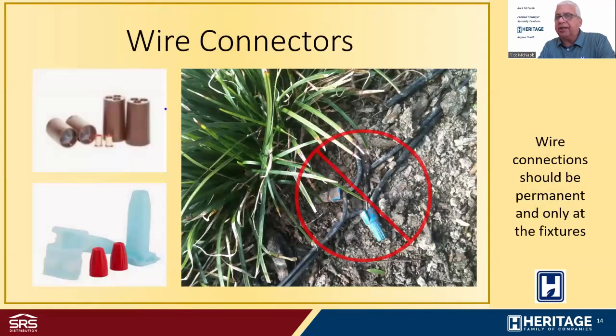The next component is wire connectors. There's several types in the market. Some are better than others. Some are permanent, some are not permanent. So the ones on the left-hand side of this screen, the ones on the top are a crimp style connector. The ones on the bottom are a tube type connector. Both of these are considered to be quality, waterproof, permanent connectors. We don't recommend the twist-on connectors because those are meant for irrigation, and they're usually in a valve box and atmosphere, and they're not usually direct buried. So we don't recommend a twist-on connector for professional outdoor lighting.